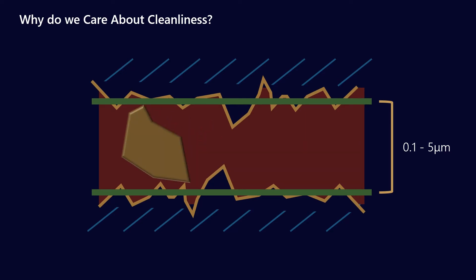But what about soft particles? If you imagine some sludge passing through your system — when it reaches a point where the flow is occluded, it can actually just morph its shape and continue to pass through. So soft particles such as sludge, air, water, or even particles which are designed to be in the lubricant like silicon-based additives, these aren't a concern from an equipment damage perspective. That's why we want to remove them from the count.